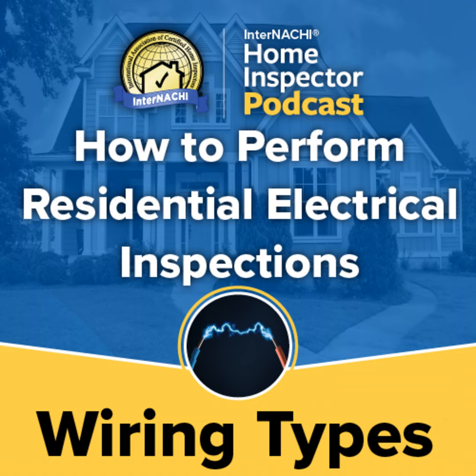The home inspector should report any knob and tube wiring as in need of further evaluation by an electrical contractor due to the following reasons. The insulation is often very brittle and leaves conductors exposed when disturbed. All circuits are ungrounded, which will not suit many modern electronics such as computers, televisions, and stereos. The conductors are often buried in attic and wall insulation. This is a problem as they were designed to work in free air. The wire gauge is commonly 14 gauge only, which is not sufficient for most modern household needs. It's very common for knob and tube wiring to have been added to over the years, and it may contain many splices outside of approved enclosures. Originally, joints in knob and tube were all spliced, soldered, and taped outside of enclosures.